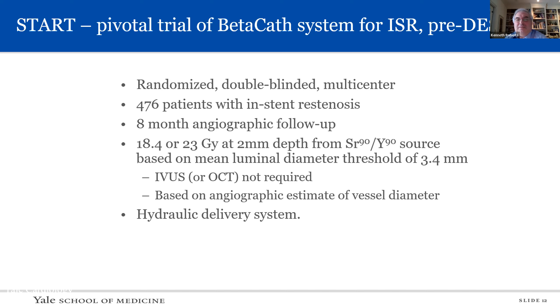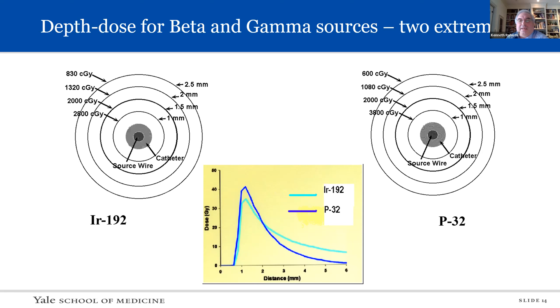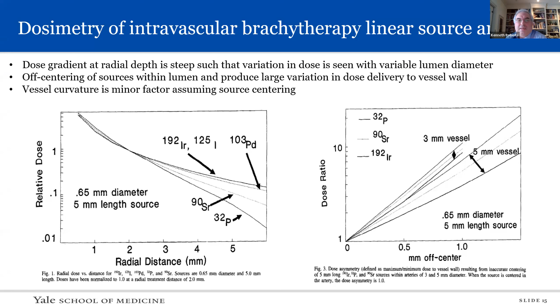Wanted to emphasize the dosimetry. The dose fall off from a single linear array of radiation sources used in intravascular brachytherapy has a very sharp drop off in dose, as I think all radiation oncologists appreciate. The 2 extremes are, I guess, iridium, less fall off, versus P32, and strontium-90 falls in the middle. There are definite dosimetry issues with non-centering of the source array, and that happens more frequently than we desire. Ideally, you'd want to have the source train right in the middle of the vessel, but the BetaCath device isn't designed to have a centering catheter. So there's a lot of variability in the dose being delivered in the catheter.